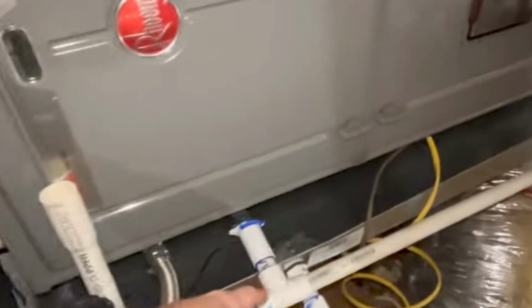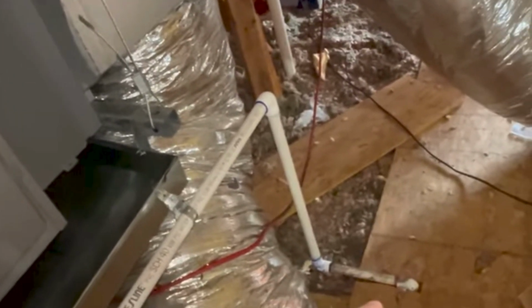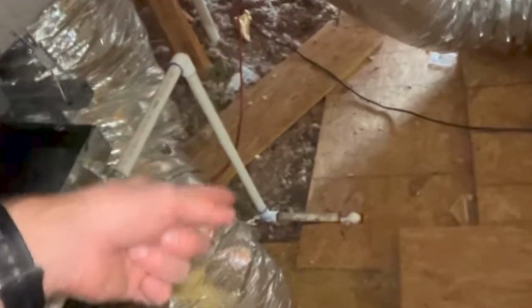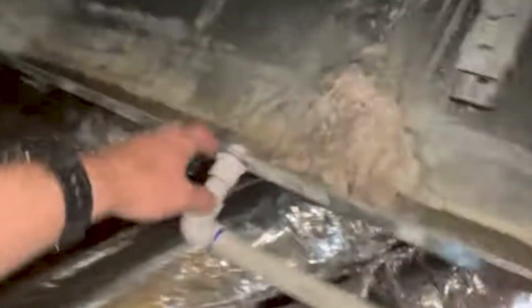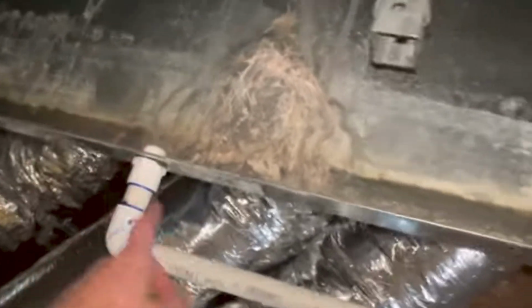Come to find out, the drain line was very backed up, and the evaporator pan was backed up with water, making its way into the supply box, I believe. The water was collecting in the insulation and steadily dripping down over time.